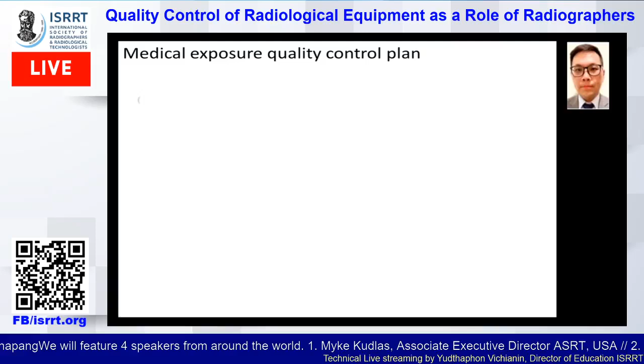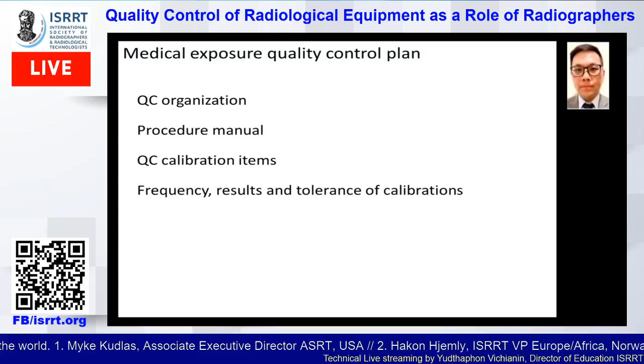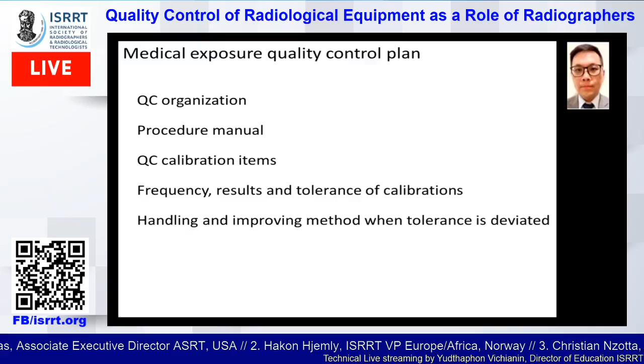The medical exposure QC plan should be approved by the AEC. It should include the QC organization, procedure manual, QC equipment, QC calibration items, frequency, results, the tolerance of the calibrations, and the handling and improvement methods when the tolerance is exceeded.